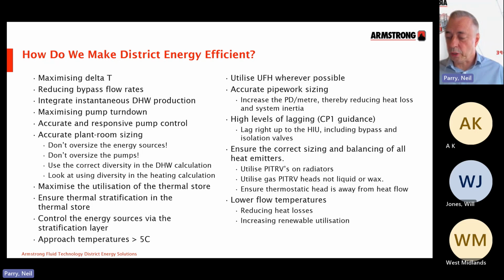So any noise, you're not going to hear much at all, because you're going to be running a bath typically. That's what's creating that high primary flow rate, so you're not going to hear that. And secondly, as for erosion, the peak occurs for 10 to 15 minutes in a 24-hour period, so it hardly ever occurs at that high velocity. So for high levels of lagging, again, I'd say use the guidance in CP1, which promotes a thicker level of lagging than is typical in most of the standards.